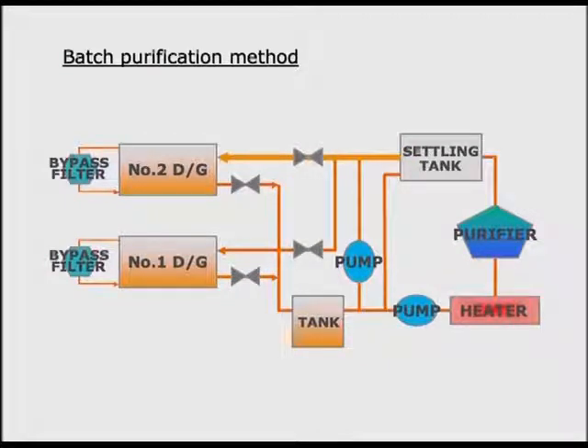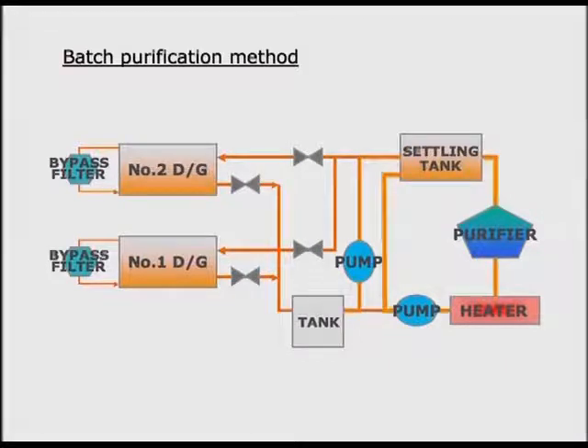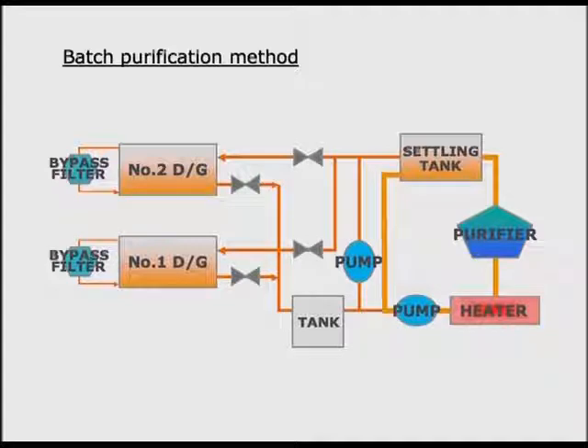Let the already cleaned lube oil flow to number two diesel engine generator and transfer the used lube oil to the settling tank. In preparation for the next replacement, conduct the cleaning treatment for the used lube oil, setting the cleaning time so that the lube oil of the settling tank flows to the purifier 20 times or more.